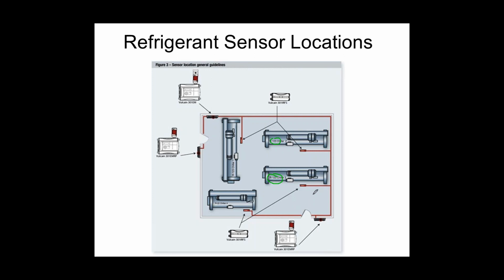So typically one sensor per machine, and a panel on the interior section of that room that has a visual blinking alarm with strobe lights and an audible siren alarm. And then outside each door, I need to do the same thing. I don't have to have a panel per se, but I have to have the strobe light and the sounding horn. A lot of times that gets accomplished with another panel. They're all interlocked together, so all of them are always alarming at the same time.